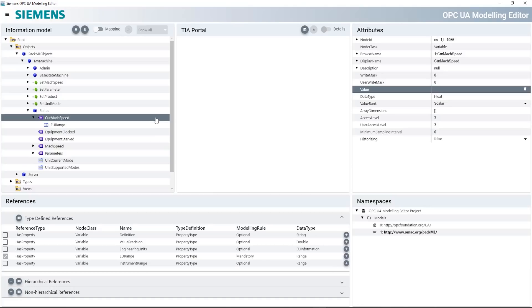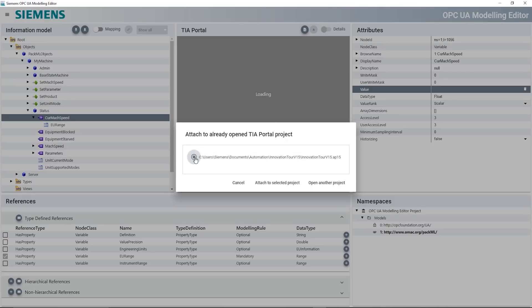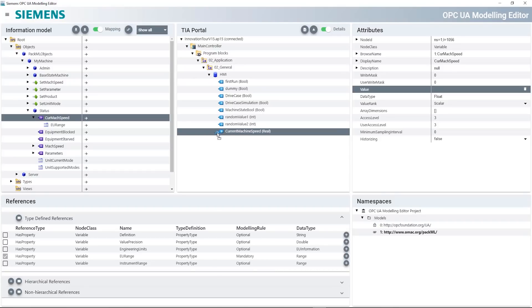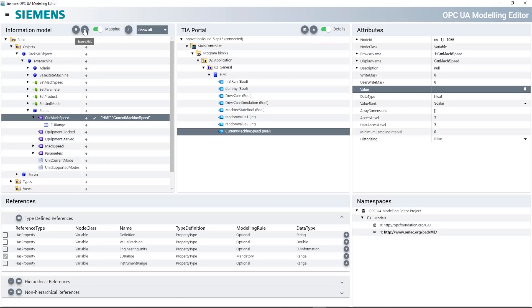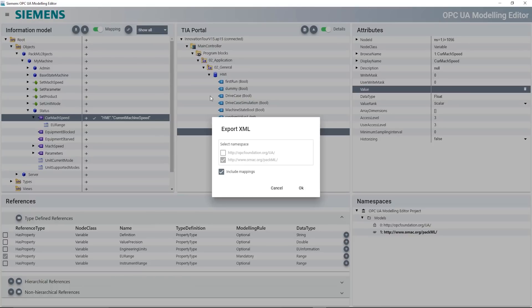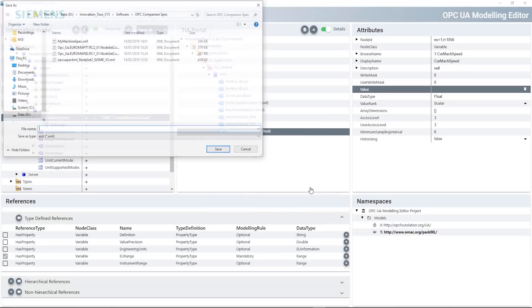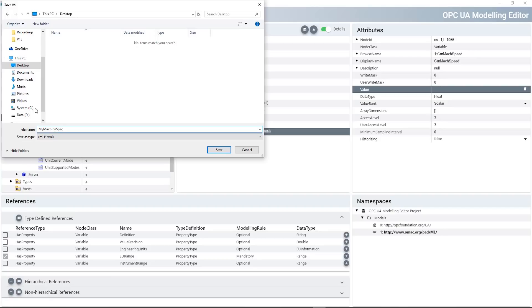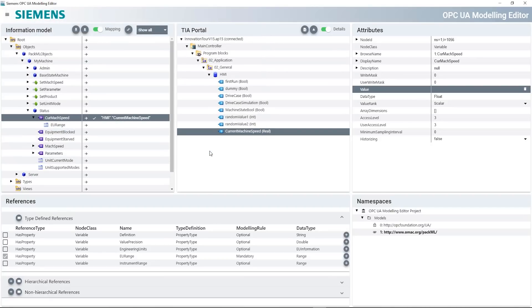Once the data interface has been modeled, the structure still needs to be linked to the data from the S7-1500. SiOME provides direct access to TIA Portal data for this. After browsing through the data, it can easily be linked to the structure of the companion specification by dragging and dropping it. When the interface is fully modeled, an XML file — which is then integrated into the S7-1500 as the OPC UA Server interface — is exported. Once the program has been downloaded into the controller, the interface is available for access. This is how easy the integration of an OPC UA companion specification can be.